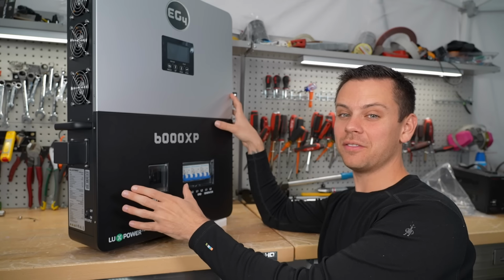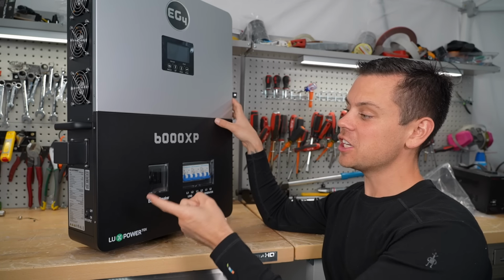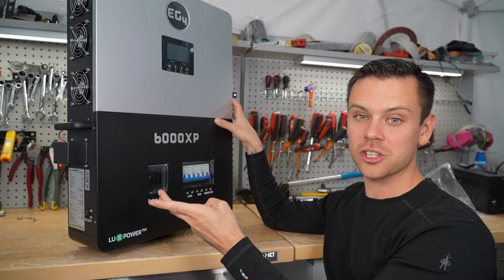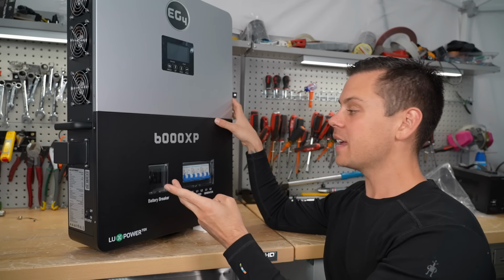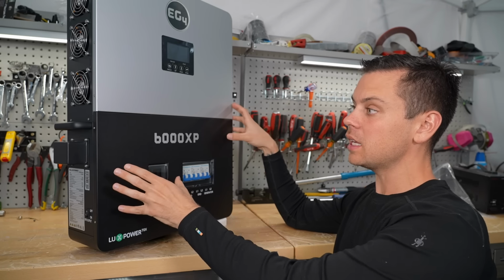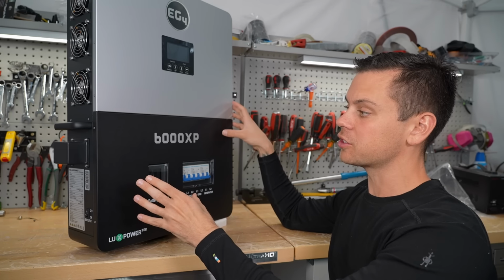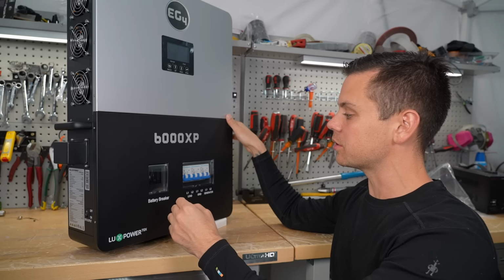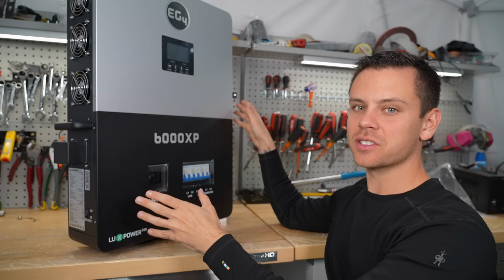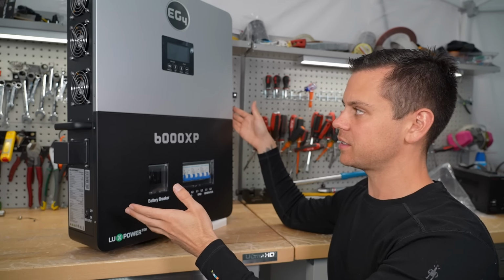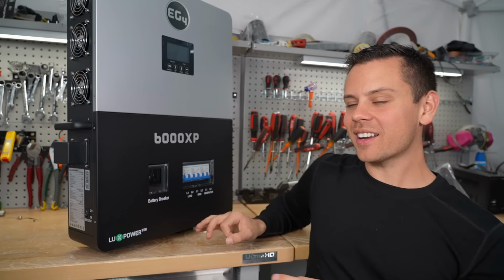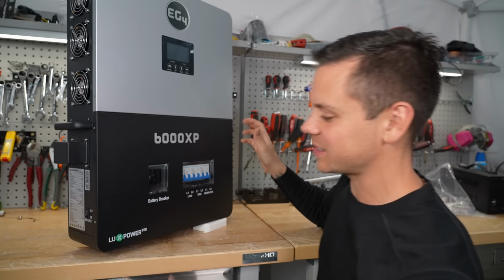Also, it has safety features that no one else has. GFCI and even arc fault detection on the MPPT. And it has its own disconnect, so it should be up to code. I'm not sure if it's certified yet, but I'm pretty sure they're going to be doing that. They usually don't add those features unless it's actually going to be certified to that standard. Anyways, that's enough talking. Let's open it up and see what's inside.